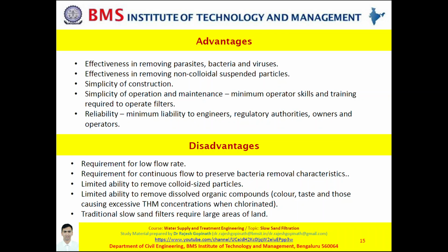However, the disadvantages which follow are, it has a requirement that you need to provide a low flow rate. Obviously, even the rate of filtration is also very less. And as I discussed before, it is not capable of removing color, taste or odor. And it has a limited ability when it comes to removal of colloidal sized particles. Most importantly, the space which is occupied by a slow sand filter is very huge, which means it requires a large amount of land.